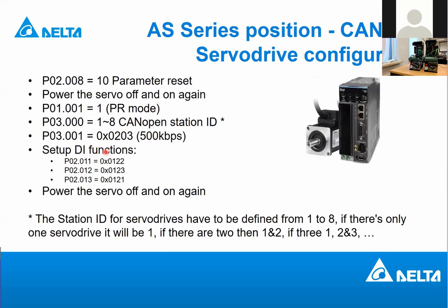is the digital input functions. You could see on the screen there is an alarm. By default, parameter 0211 to parameter 0213, the digital input is normally closed. That is why you see alarm 13. If you can see the video, you see alarm 13 on the screen. So to disable that, we change this 0 to 1. If we change it to 1, it means normally open. Now it's like the digital input is engaged. We have to disengage. So if we disengage by writing 1, what is going to happen? The alarm will be cleared. So let's go to parameter 0211 up to 0213. Then the alarm will be cleared.